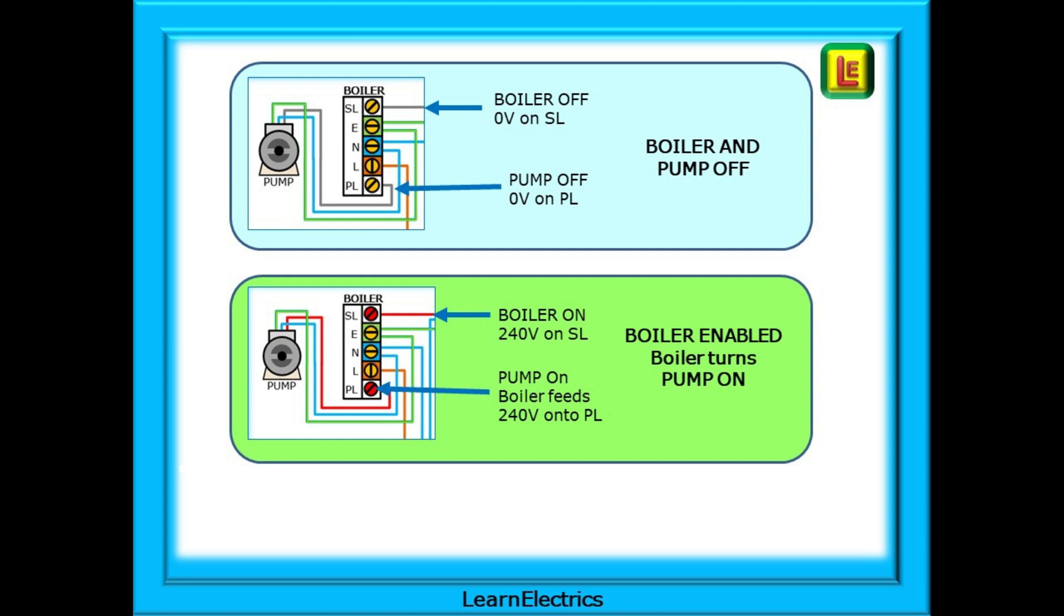The boiler and the pump work in unison with each other. If the boiler is off, the pump will also be off, as shown in the blue box. The green box shows the boiler enabled. 240 volts appears on the SL terminal and switches the boiler on. An internal connection in the boiler feeds 240 volts to the pump and the pump starts. Some boilers have an overrun facility. When the boiler turns off, the pump continues to circulate water for a few minutes to allow the hot water in the system to cool slightly, thereby avoiding heat damage to sensitive parts. Some boilers don't have this and we will look at this on a later slide.